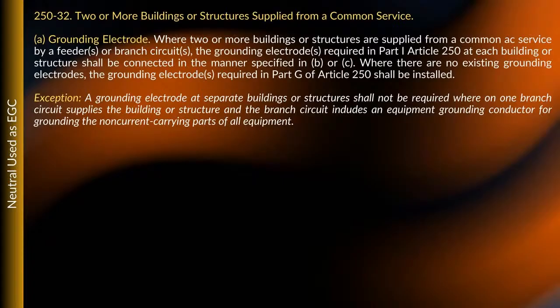But the problem we got into is if a coupling or a connector came loose. So they made some changes in 250.32, and when you looked in, they added this: where you had two or more buildings or structures supplied from your common service, the grounding electrodes required in Part 1 of Article 250 to each building or structure shall be connected in the manner specified in B or C.